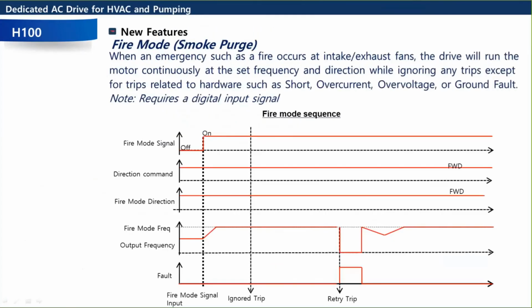So here's a feature that's more geared towards the HVAC guys, which is fire mode. You may hear it called smoke purge or fireman's override or something like that. So whenever there's an emergency situation, such as a fire in a building and it's connected to your fire switch or whatever, your intake and exhaust fans are typically going to want to run continuously, and it's going to be like a run to fail.